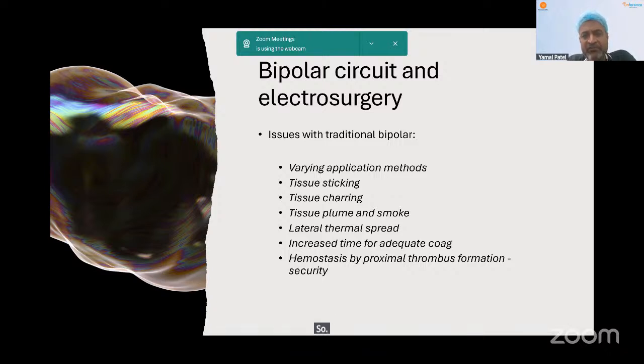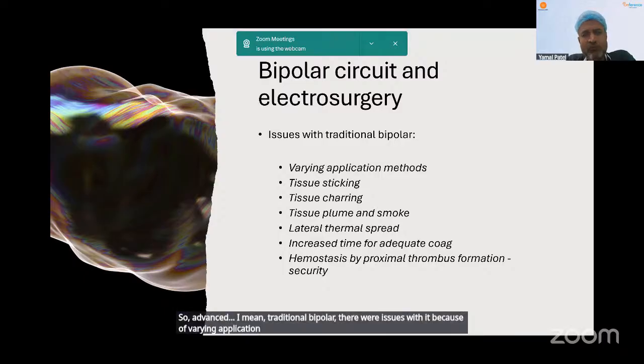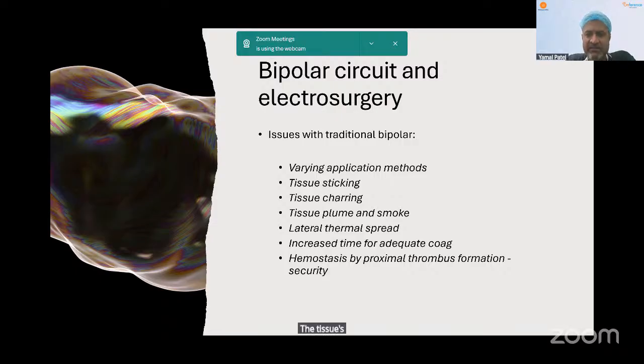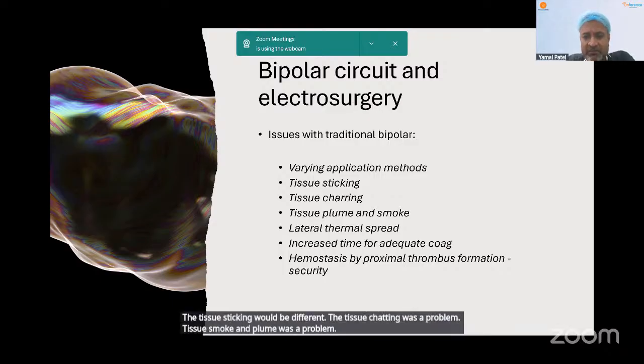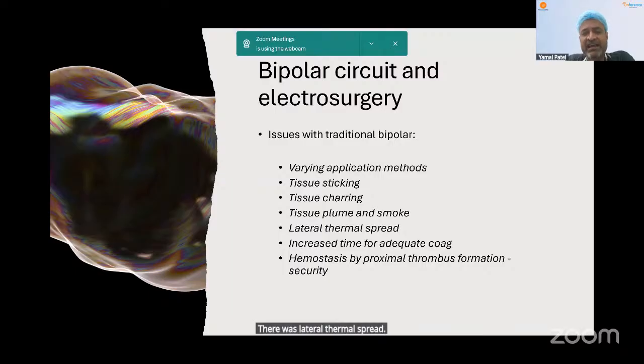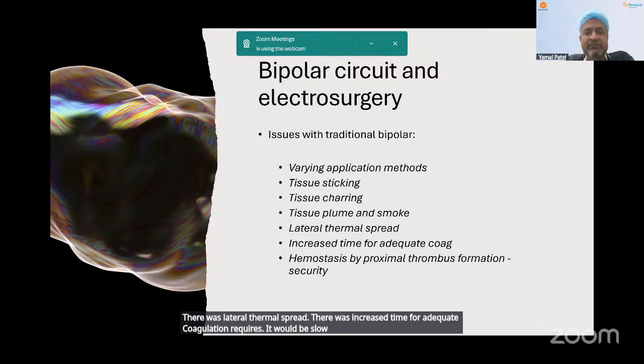Traditional bipolar had issues because of varying application methods. People would apply it for a long time, another would apply it short, another continuous, another intermittently. So there is variation. The tissue sticking would be different. Tissue charring was a problem. Tissue smoke and plume was a problem. There was lateral thermal spread. There was increased time required for adequate coagulation. It would be slow. And the hemostasis was actually by proximal thrombus formation. Hence, the security of that clot would not be that high.